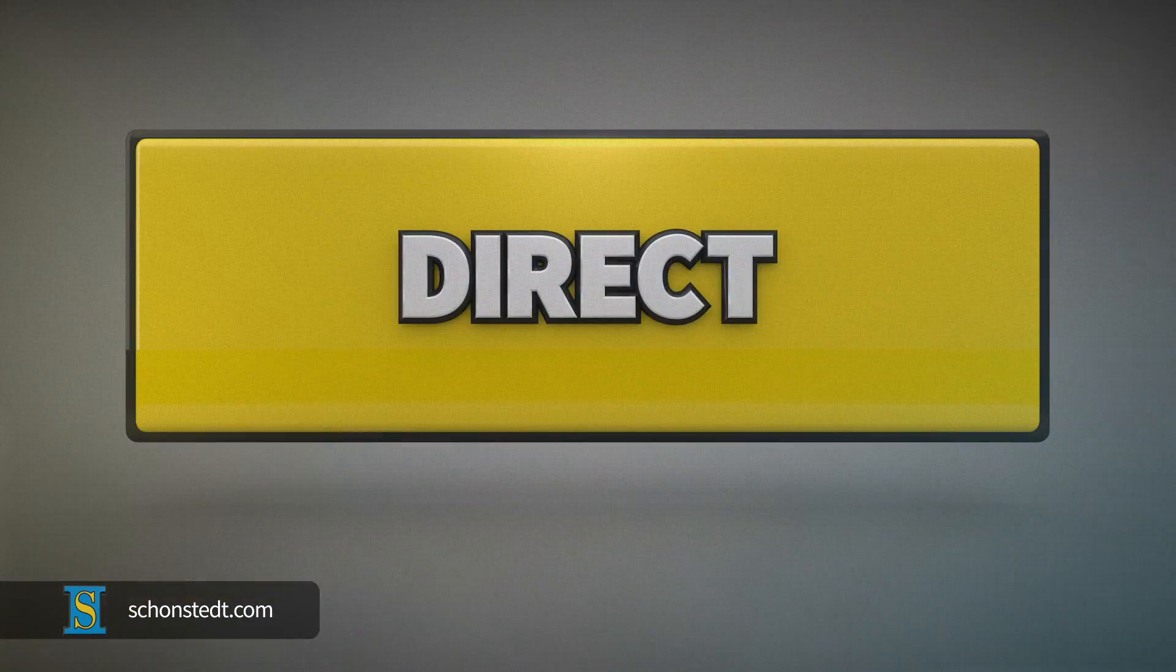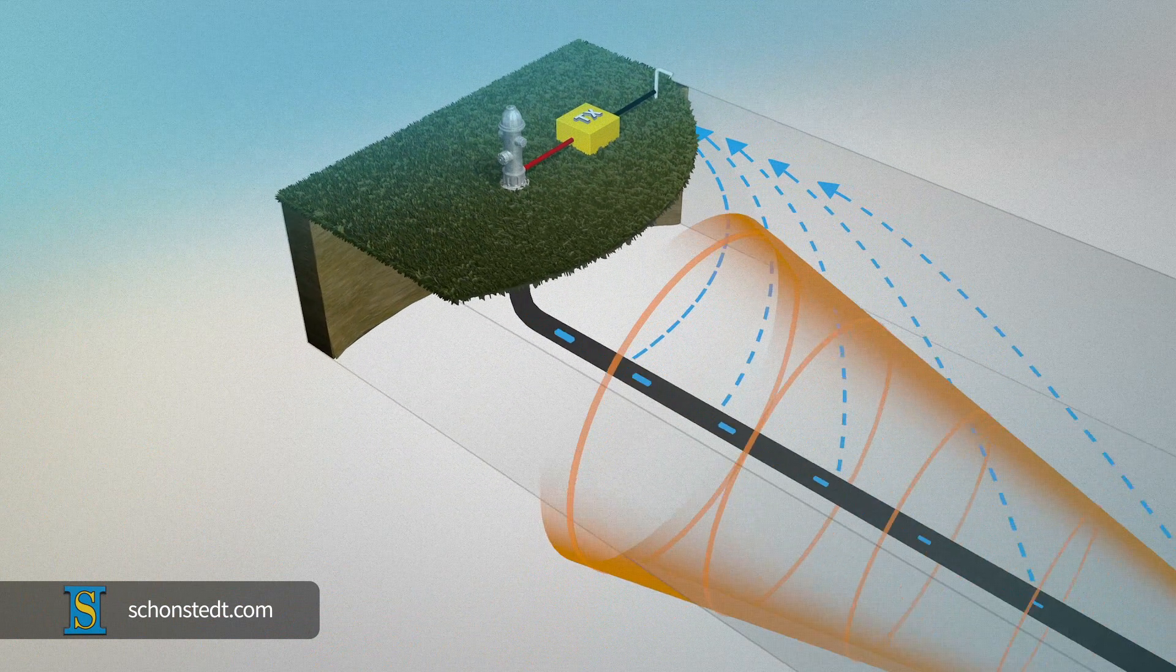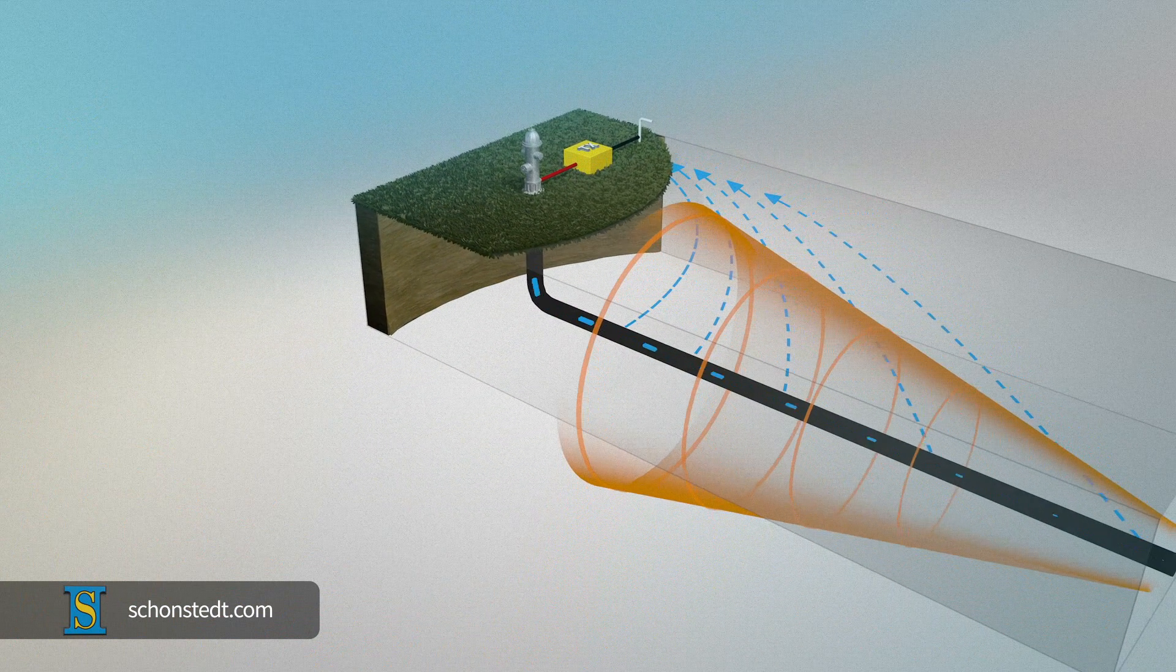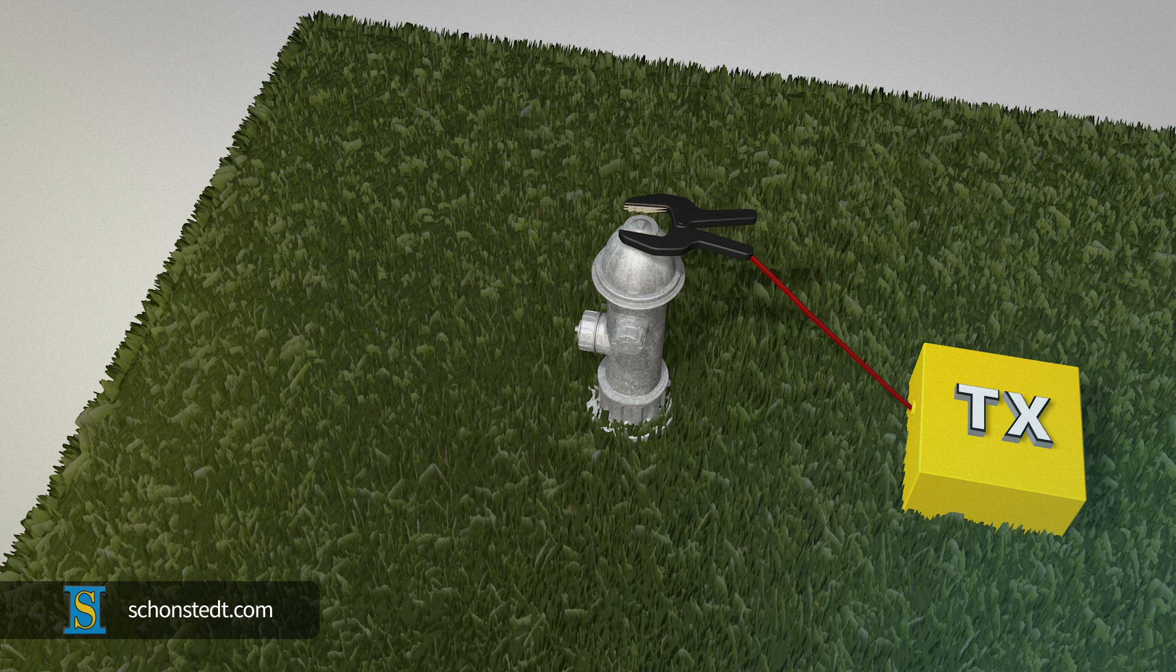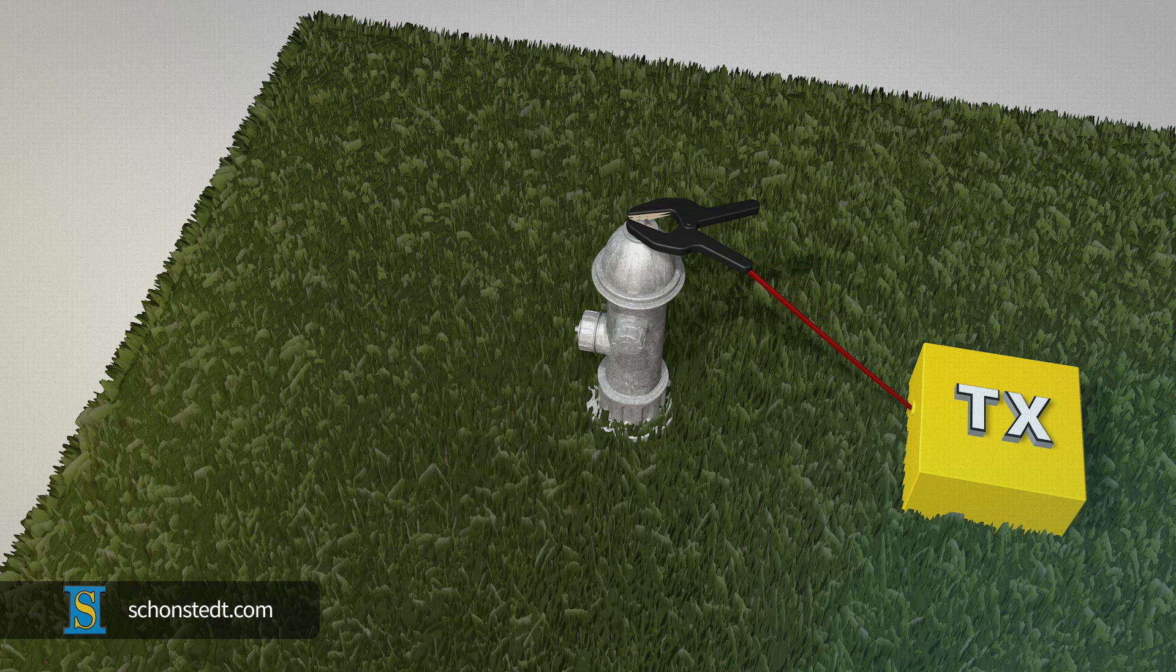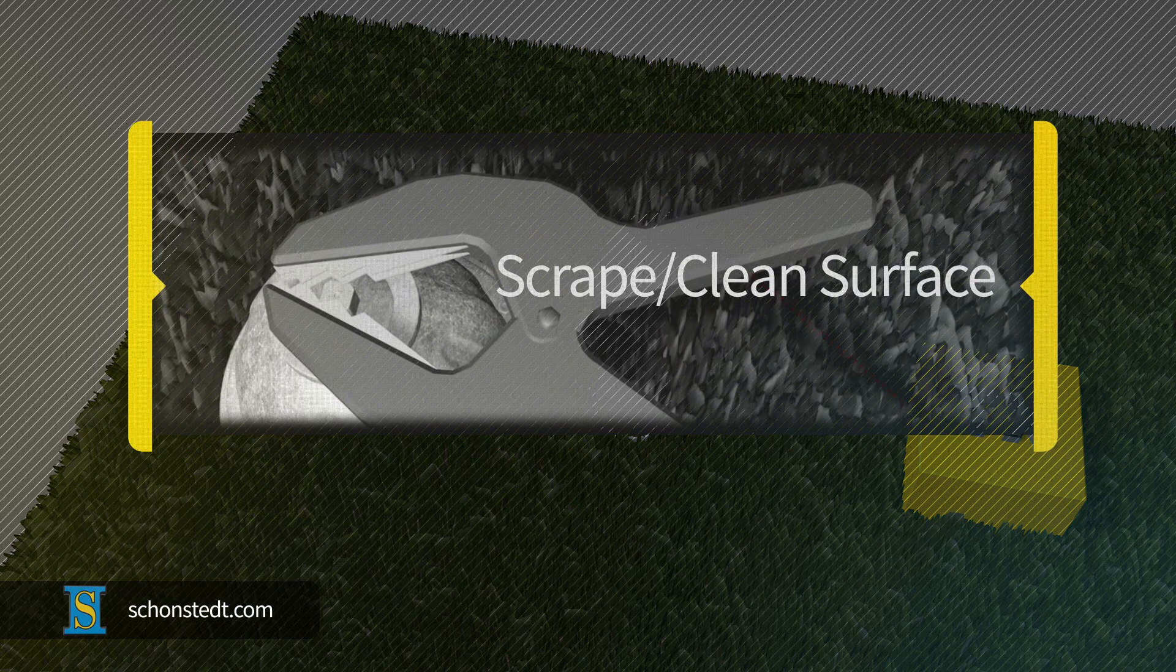With the direct method, you must make a direct connection to the pipe or cable being located. This concentrates the signal on the targeted line. First, take the clip attached to the red cable and apply it directly to the pipe or cable you're trying to locate. Make sure there is a good metal-to-metal contact. For best results, you may need to scrape or clean the surface at the point of contact.